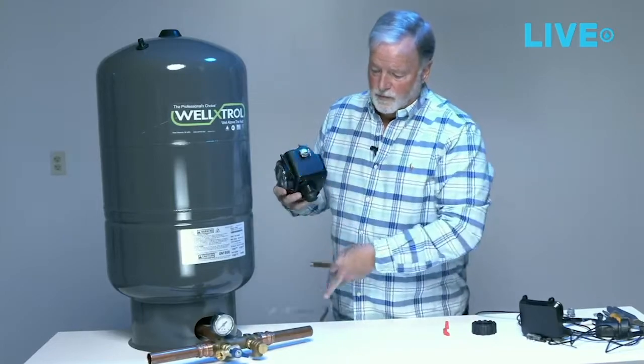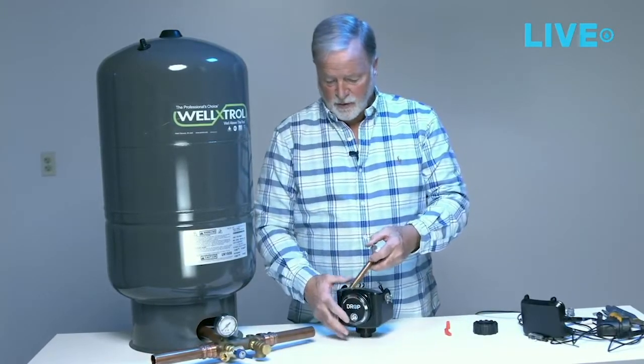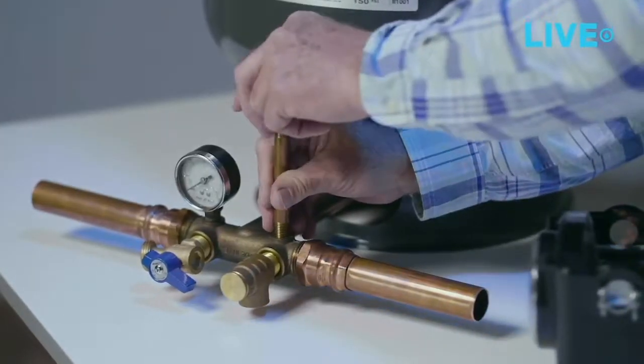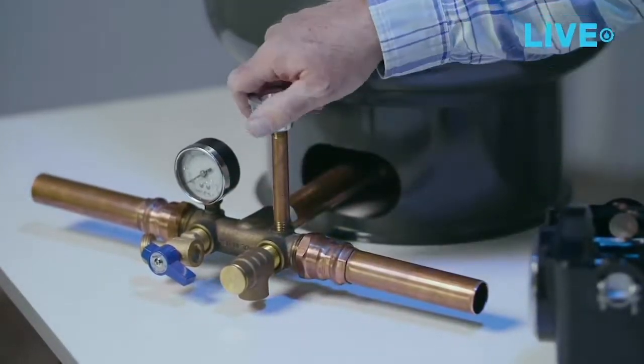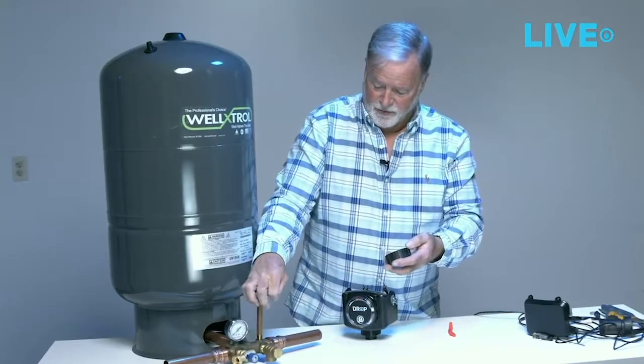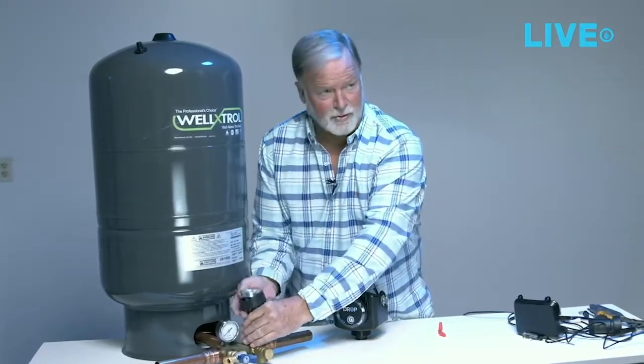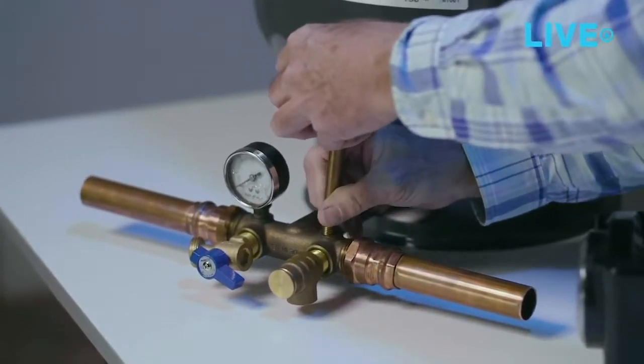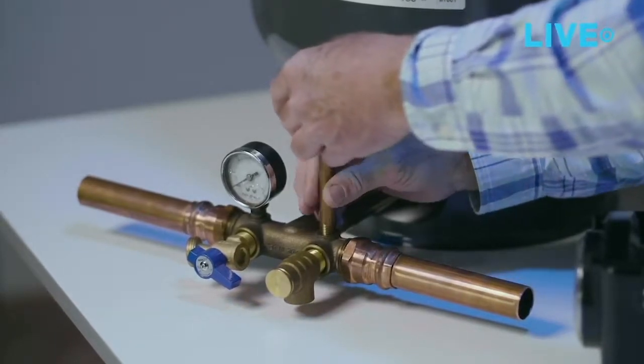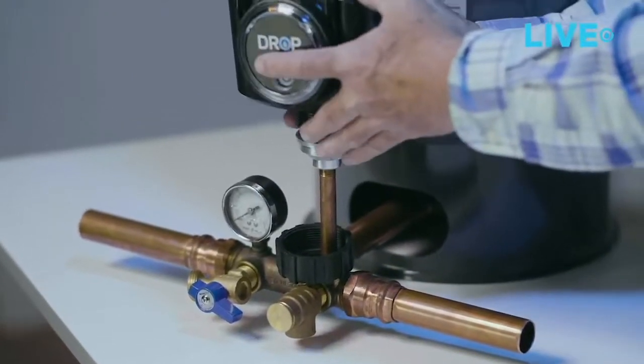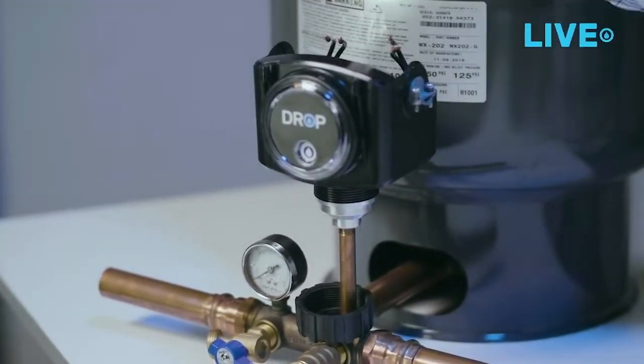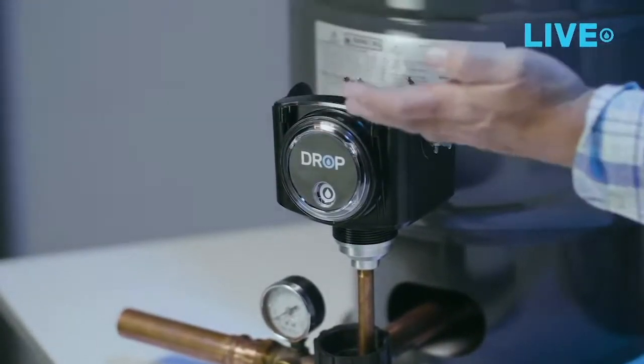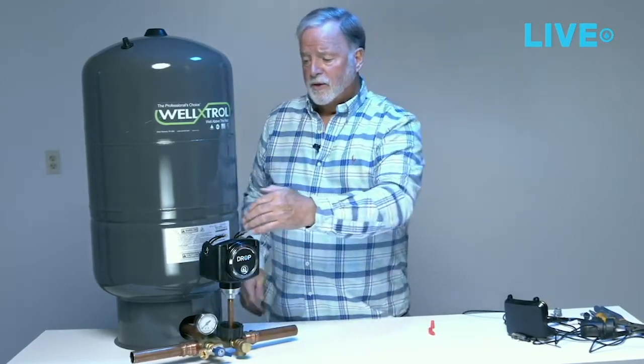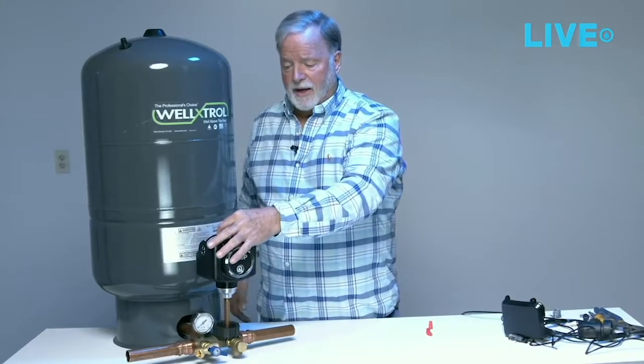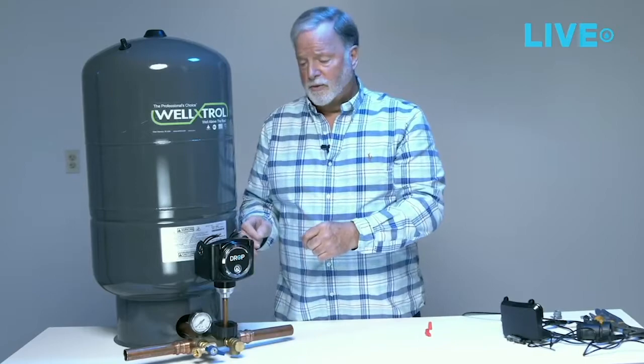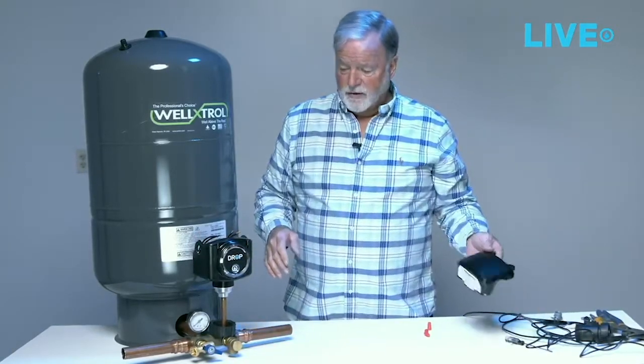The next thing you would do is, because you don't have to worry about spinning this, you put the stem in, the pressure sensing stem in, on its stainless steel base, and you don't want to forget putting the nut on first, because then you have to take it off. I did that just to show you that you don't want to do that. So once this is properly installed and sealed, then you can simply just plug this back down on. Then you would bring your wires in from the side, make it up, and as we talked earlier as well, because you may have to be concerned with a voltage drop and a long run to the motor, you can bring a nice size gauge wire through here and not have to fight very tiny little terminal strips like you might find in other devices. So the installation is just that simple.